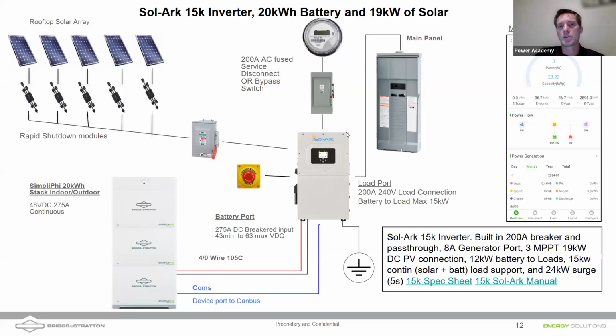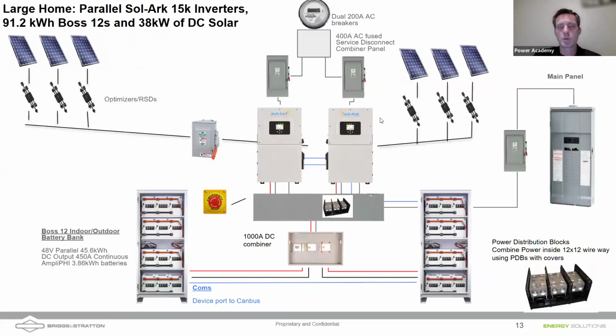So you could either be connecting the Sol-Ark to your main load center or use a bypass switch to connect utility to the main load center. This is a different way to wire it. It's optional. Of course, you can parallel these inverters. So if you've got a big home with lots of loads on it that might have 400 amp service, you can parallel these inverters. So we're showing a larger system here with several strings of solar and a couple of our Boss 12 battery cabinets.